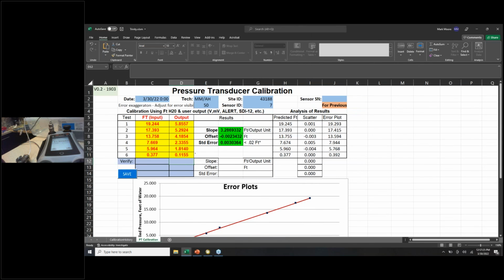So this is how we would do a calibration, and this is something we do in the field. Anytime we're working with a PT, you want to do at least 6 measurements, and you want to test the full scale. So if your PT goes up to 50 feet, you want to calibrate it to 50 feet. If your PT only goes to 10 feet, you want to calibrate it to 10 feet. But what you do is you do 6 points, you compare it to your known good, and with your known good, you can calculate a slope, offset, and standard error.